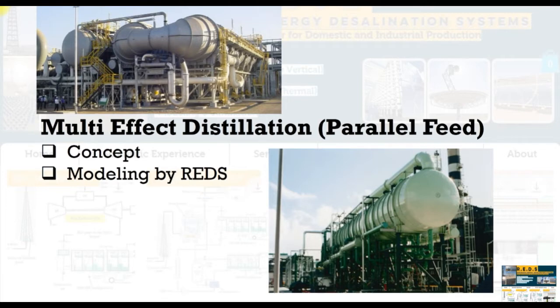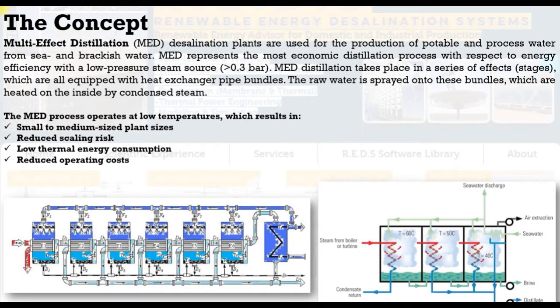What is the concept of Parallel Feed Configuration and how we can run our model and simply extract our data. Multi-Effect Distillation plants are widely used for the production of potable and processed water from sea and brackish water, which represents the most economical distillation thermally with respect to energy efficiency and specific power consumption, because it uses relatively low pressure steam source around 0.3 to 0.5 bar. We are talking about 60 to 70 degrees Celsius, allowing some kind of processed heat with MED.